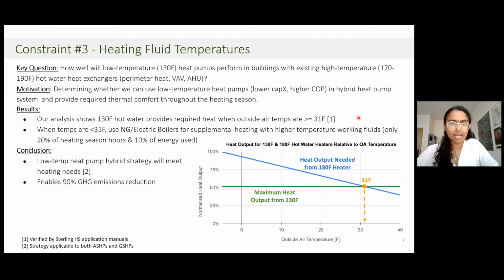And so now we're looking at a hybrid system, which is sized for a heat pump for temperatures greater than 30 degrees Fahrenheit. We're using a low temperature heat pump there and looking at the natural gas boiler for supplemental heat on the coldest days. And as a note, this is still able to achieve that 90% decarbonization that we mentioned.